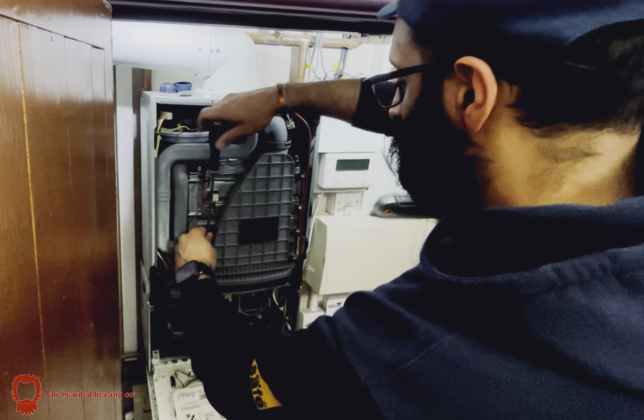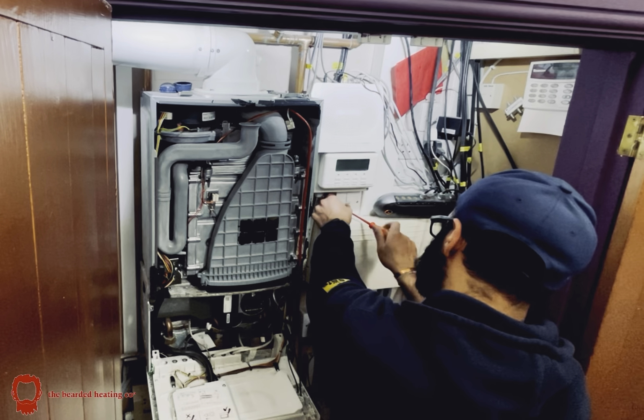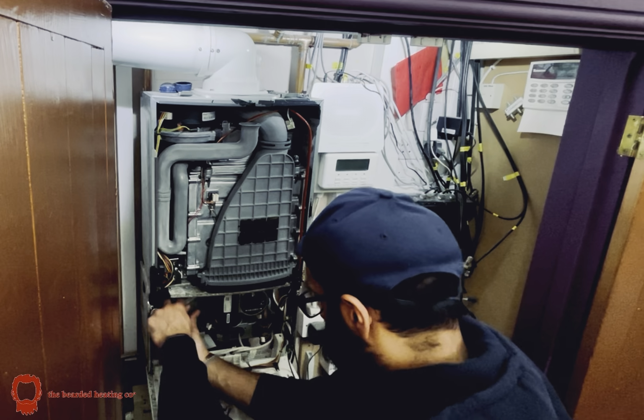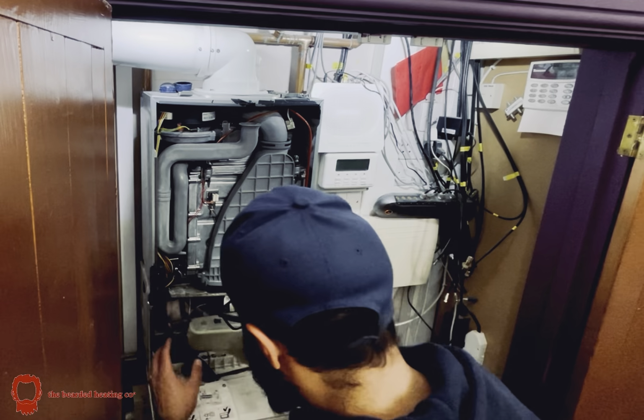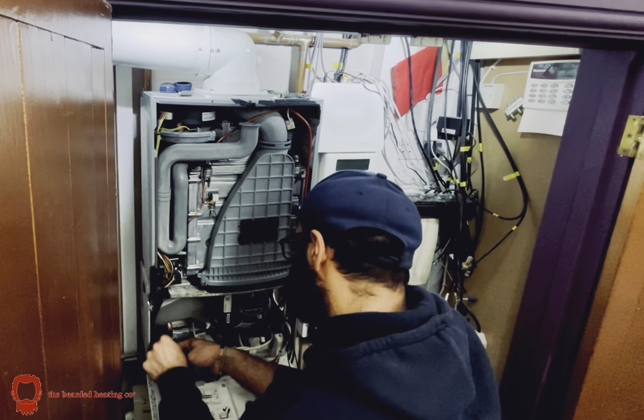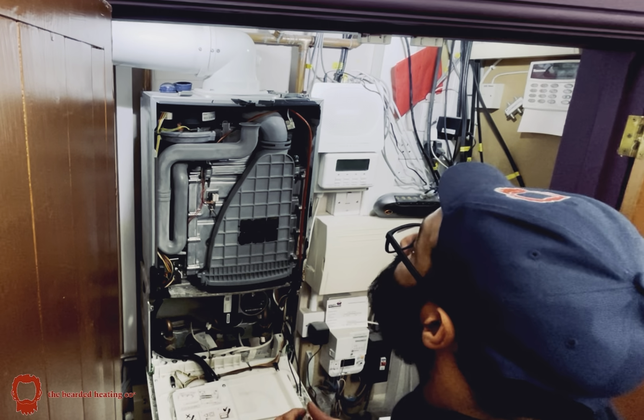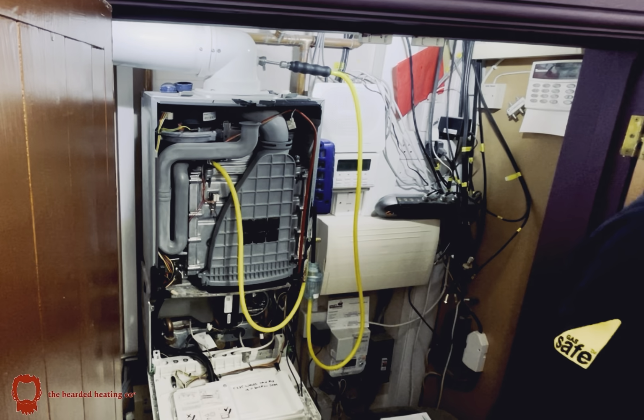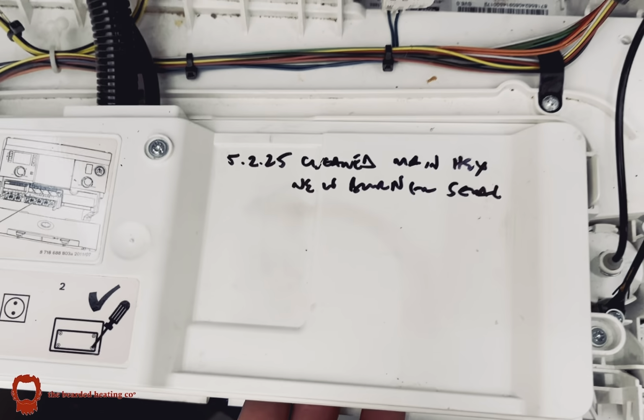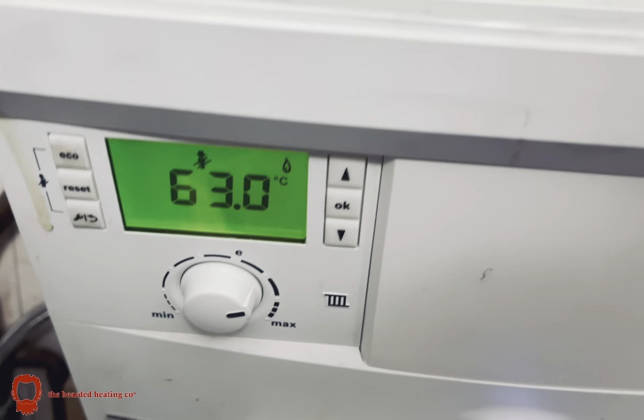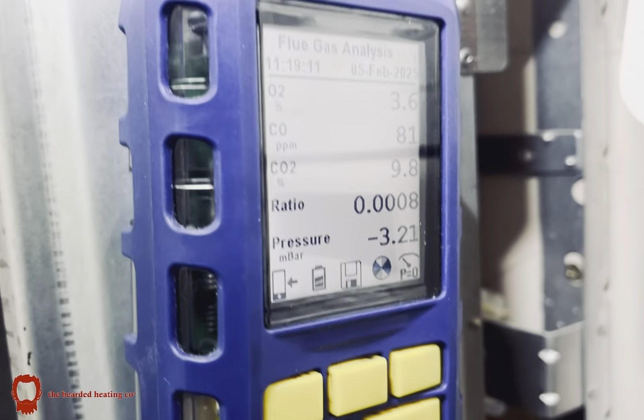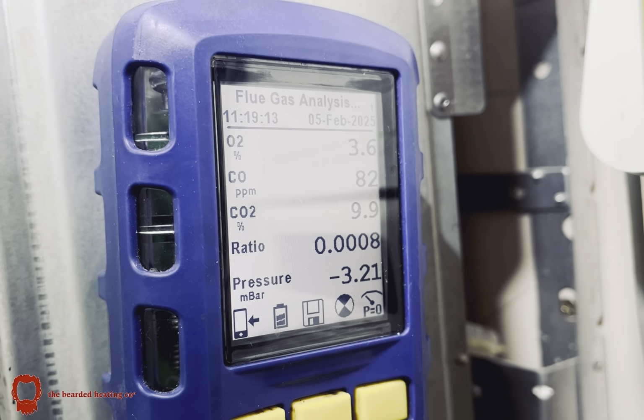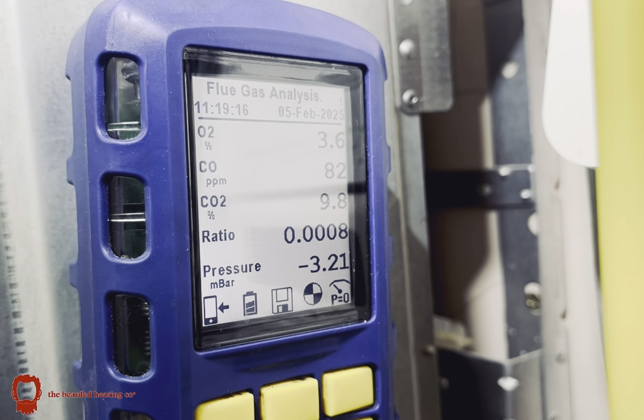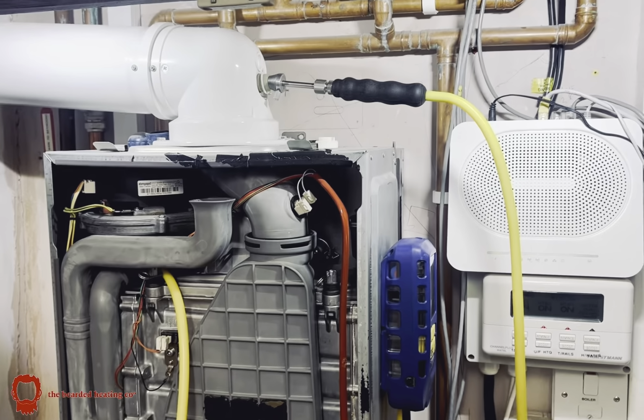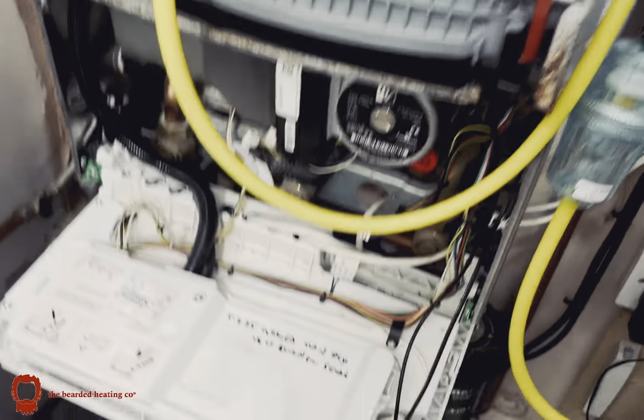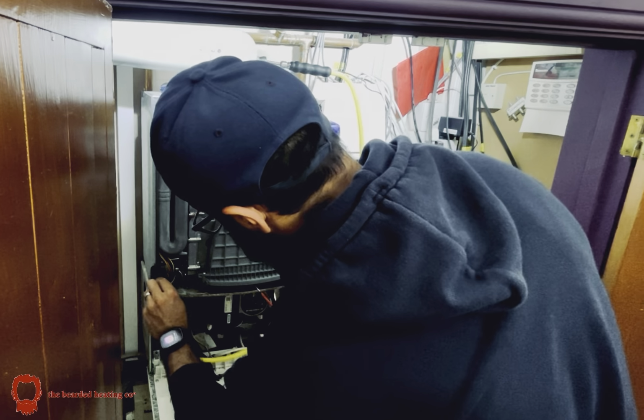I turned the power back on and then I realized that I hadn't washed the condense trap out, so I turned it back off, removed the condense trap, and washed it out. Now put the power back on. And now to carry out my negative fan pressure test again. There I just wrote what I've done on the boiler. Boiler's in max fire, and now you can see that the fan pressure is now minus 3.26. So that is a huge increase from before. And my combustion now was so much better, as it should be.